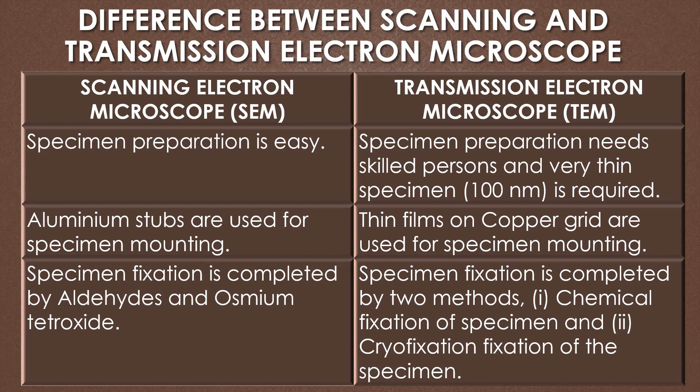Specimen preparation is easy for the SEM, but for the TEM it requires a skilled person and a very thin specimen — the specimen thickness should be 100 nanometers or below. In the SEM, aluminum stubs are used for specimen mounting, while in the TEM, thin films on a copper grid are used. In the SEM, specimen fixation is completed by aldehydes and osmium tetraoxide. In the TEM, specimen fixation is completed by two methods: chemical fixation and cryo-fixation.